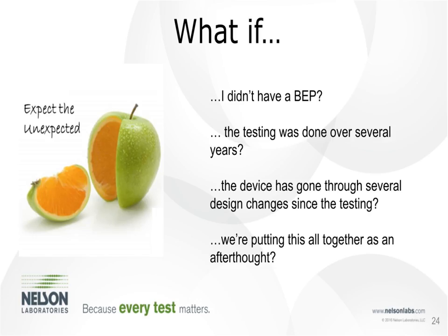What if the device has gone through several design changes since the testing? This one can be a little bit more difficult because if there were not assessments done at each design change, the relevancy of the testing done originally and the current product could be very discrepant, and so it's important to have an assessment performed of that. And so you can still do a BEP, but I would recommend that you start with a phone call with one of our consultants to ensure a path of success for that submission to make sure we're addressing that appropriately.